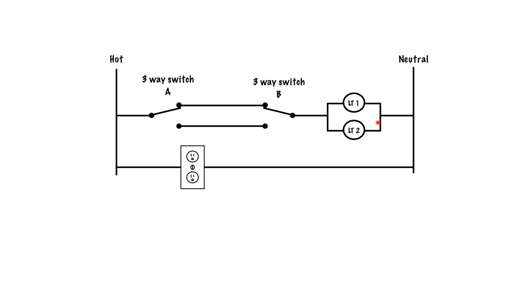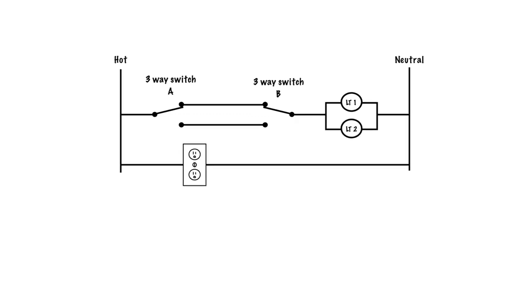As always we have the lights connected to the neutral. Down here we have a hot going to our receptacle, and from the other side of the receptacle going back to our neutral. When dealing with this circuit and trying to determine how many wires go in the pipes, the first thing we want to do is number our wires. Anything attached to that wire is going to carry the same number, and whenever we have a node — one of these little black spots — or a break in the line, or a device in the way, we change the number.